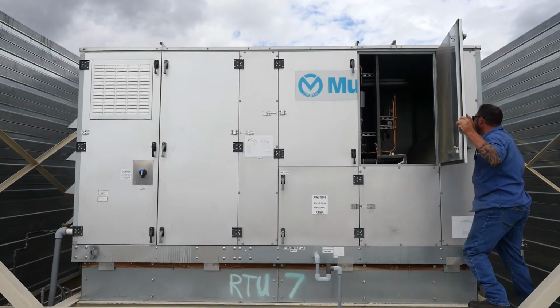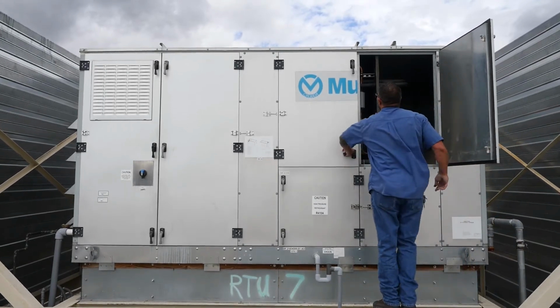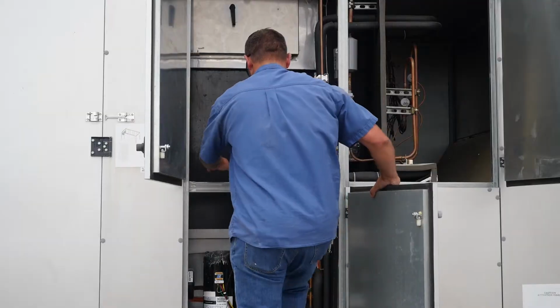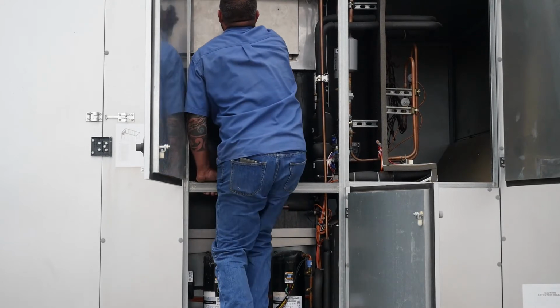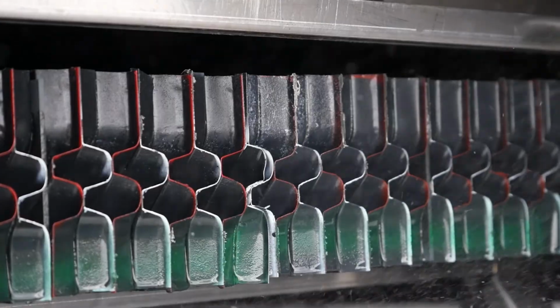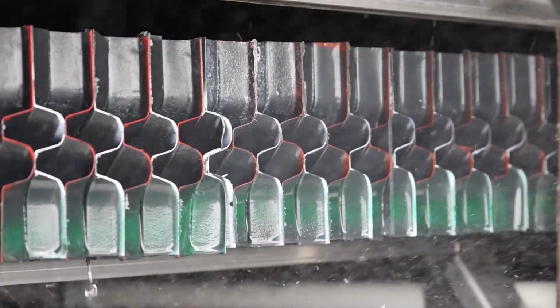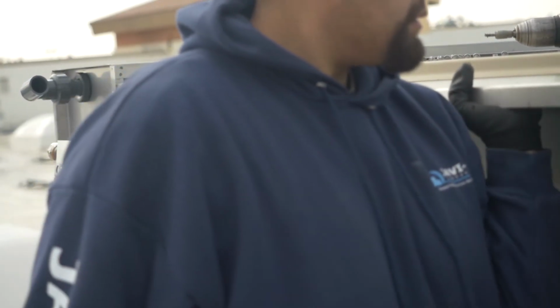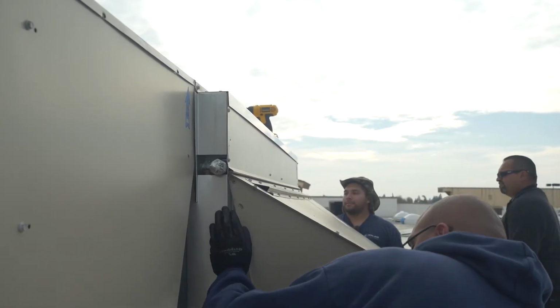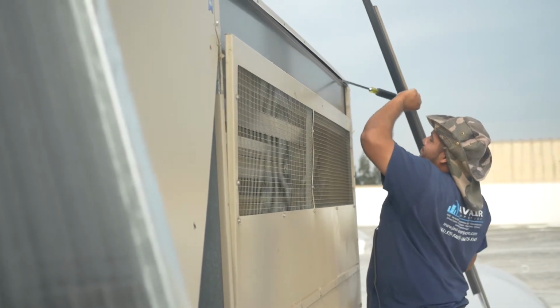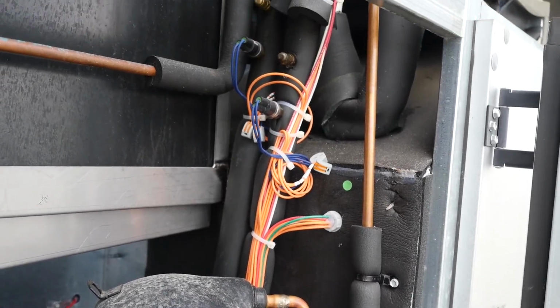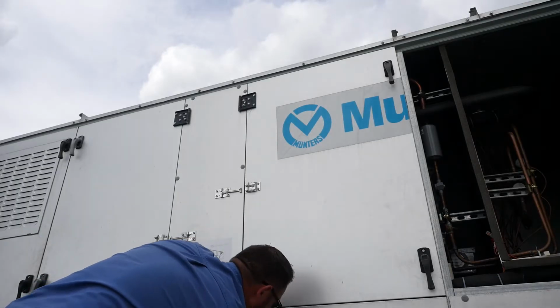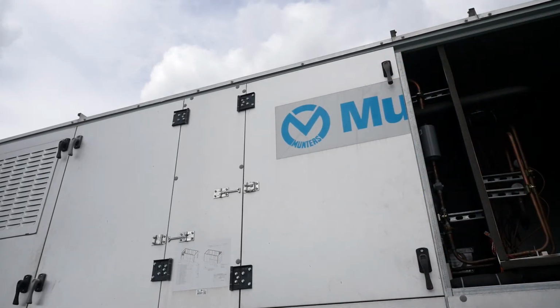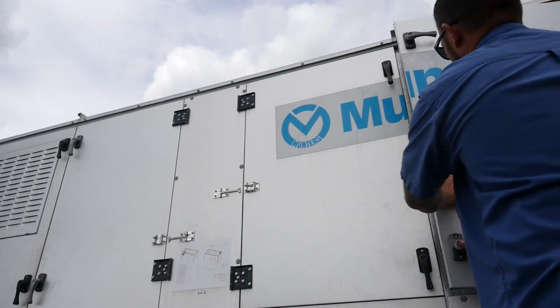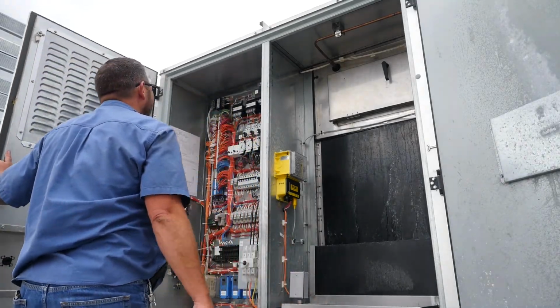Munters employs a number of methods to minimize maintenance required on evaporative components. The geometry and materials used in the indirect evaporative heat exchanger are designed to shed mineral buildup. A bleed process removes concentrated minerals from the sump water. However, like any HVAC equipment, Munters units require ongoing maintenance to ensure that they continue to function reliably. Service contracts are available from Munters. Munters Service provides on-call technical support, extended warranties, spare parts contracts, and maintenance inspection plans tailored to the specific needs of owners. As with any new technology, it is important to have a foundation of service professionals that are familiar with maintenance and system operations when problems arise. Munters employs 60-plus service technicians located all across the U.S., including several technicians located in California. Customers can access Munters service technical support through the company's website or by phone.